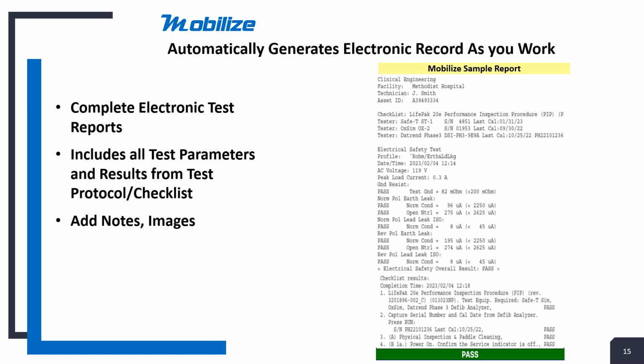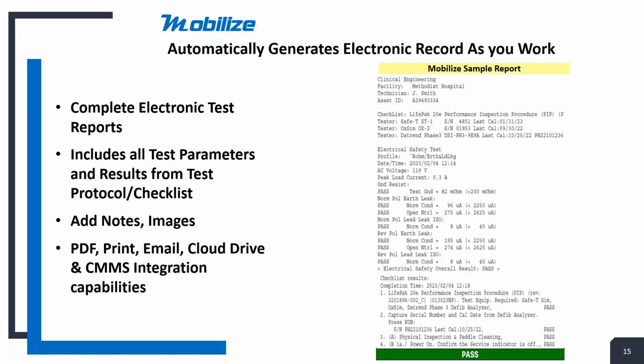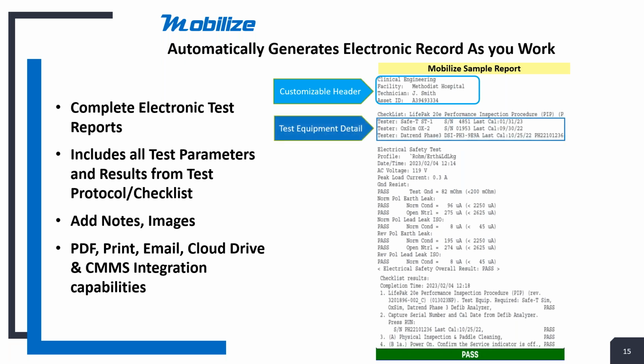Maybe any physical damage or anything you want to make a note of, you can go ahead and add that in there. And of course, the report has the ability to be exported in a variety of ways, including integrating it into a CMMS. So you can see the report has your header information in there. It lists all of the test equipment that was utilized to do this PM. So not only what model, what serial number, but the calibration date of the test equipment. So the test equipment knows its calibration date and electronically via Bluetooth sends it over and adds it to the report. This gives us real confidence in the report we've just generated.